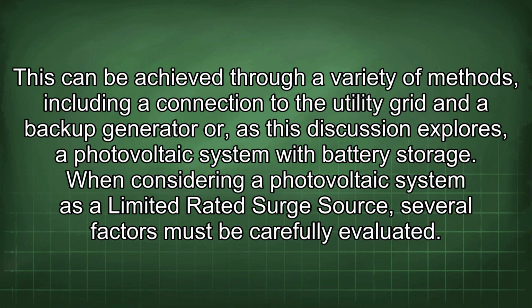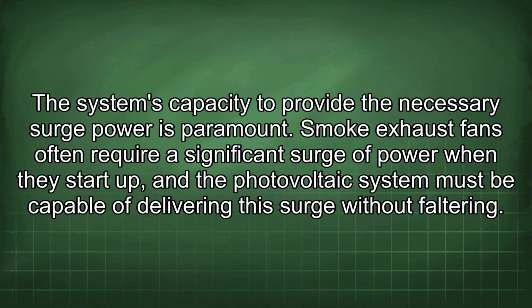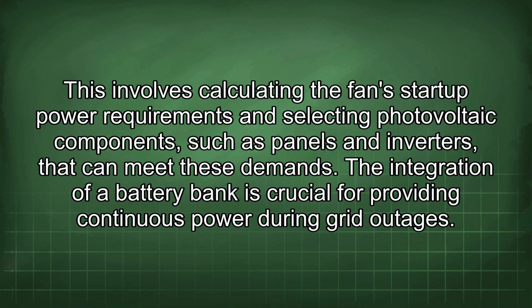When considering a photovoltaic system as a limited rated surge source, several factors must be carefully evaluated. The system's capacity to provide the necessary surge power is paramount. Smoke exhaust fans often require a significant surge of power when they start up, and the photovoltaic system must be capable of delivering this surge without faltering. This involves calculating the fan's startup power requirements and selecting photovoltaic components, such as panels and inverters, that can meet these demands.